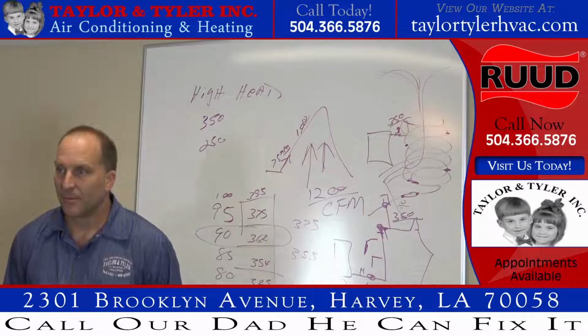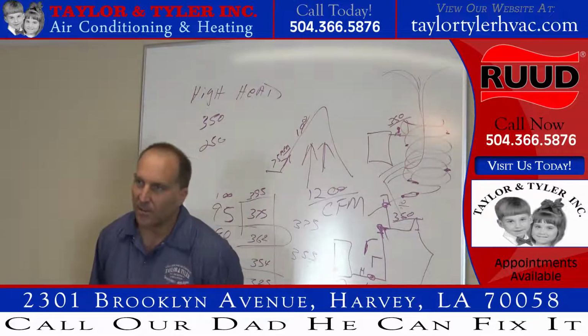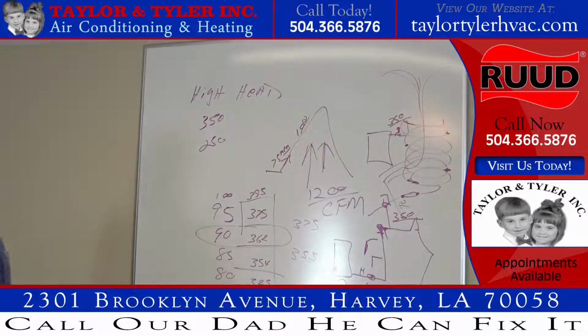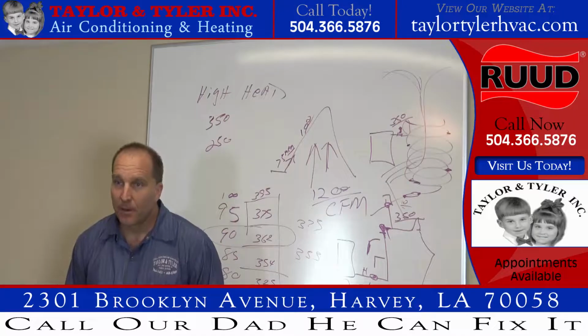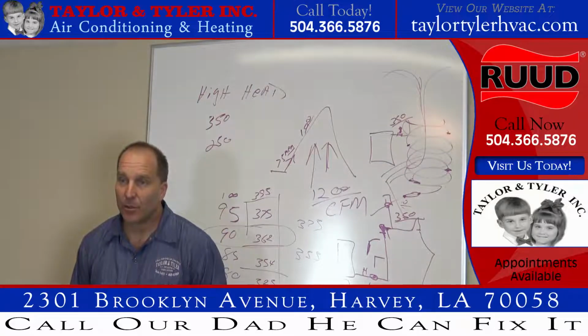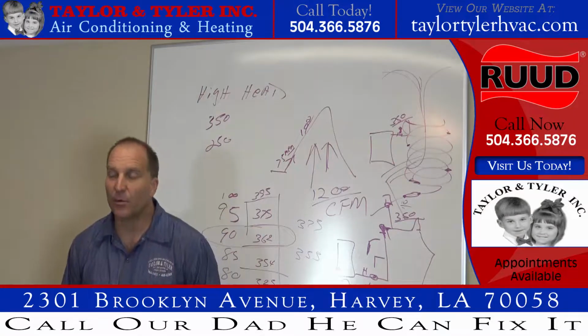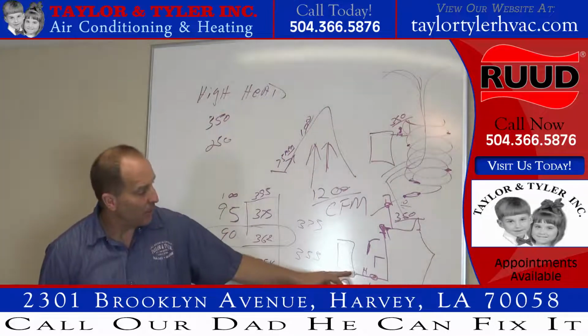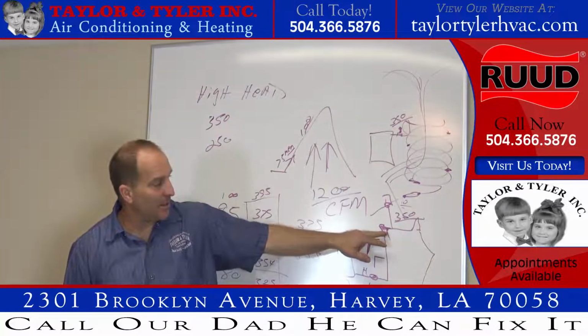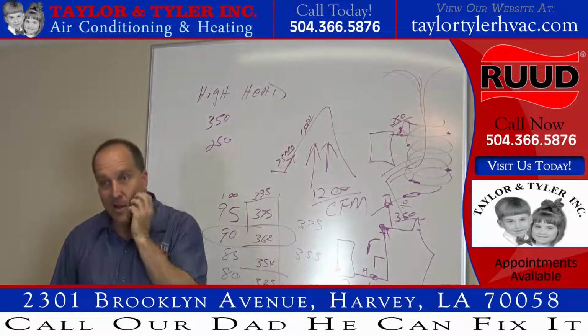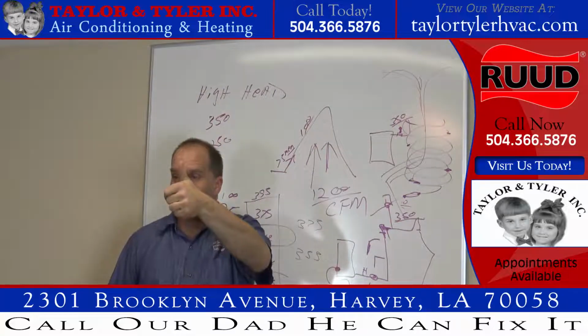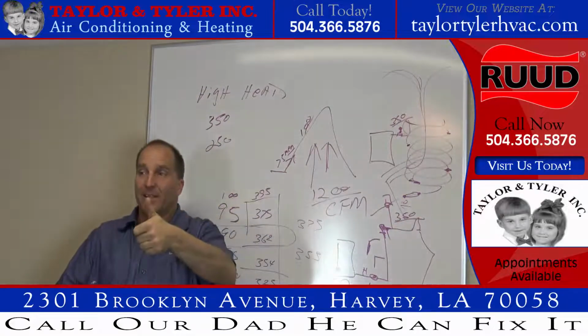Right? So you're charging the system up. Are you going to get a high subcooling or a low subcooling? I would say high. You're going to get a high subcooling because you're going to keep putting refrigerant in the system. The refrigerant is going to come over here and it's going to get restricted here, okay? So your head pressure is going to go high, your subcooling is going to go high.